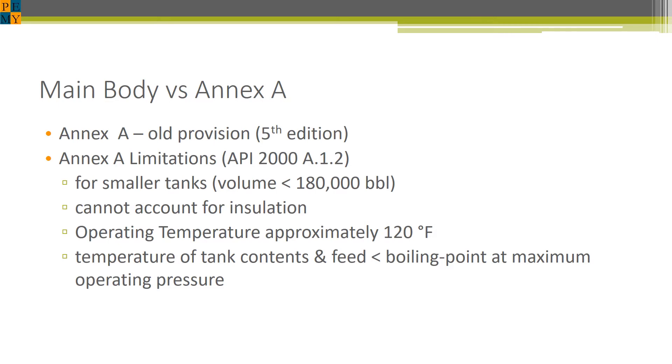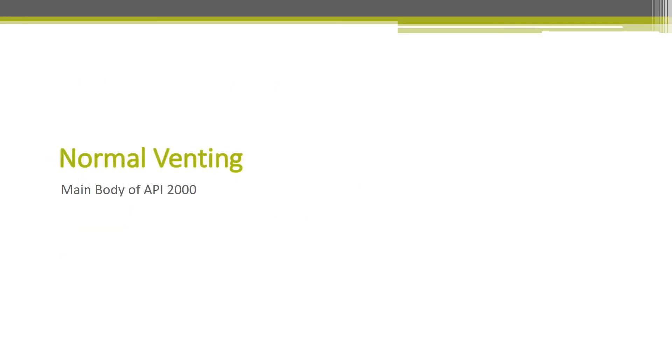Annex A can still be used under various limitations. It can only be used for smaller tanks, it cannot account for insulation, and has certain requirements in terms of the temperature that's assumed. In general, tanks that were designed under Annex A have been used by industry for several years with no incidents. However, because of this new research, it is best practice to use the main body at least for newer tanks. It is considered acceptable to use Annex A for existing tanks because these tanks were designed under Annex A.